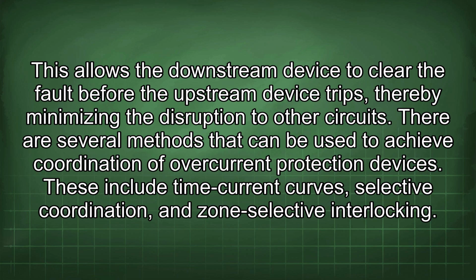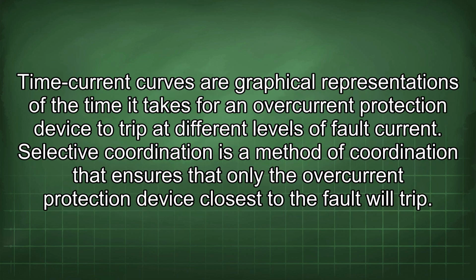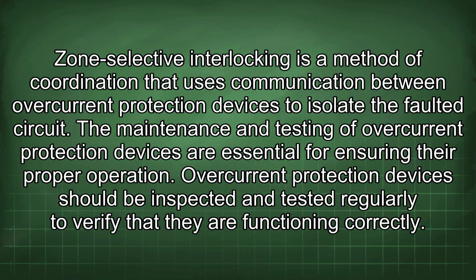There are several methods that can be used to achieve coordination of overcurrent protection devices. These include time current curves, selective coordination, and zone-selective interlocking. Time current curves are graphical representations of the time it takes for an overcurrent protection device to trip at different levels of fault current. Selective coordination is a method of coordination that ensures that only the overcurrent protection device closest to the fault will trip. Zone-selective interlocking is a method of coordination that uses communication between overcurrent protection devices to isolate the faulted circuit.